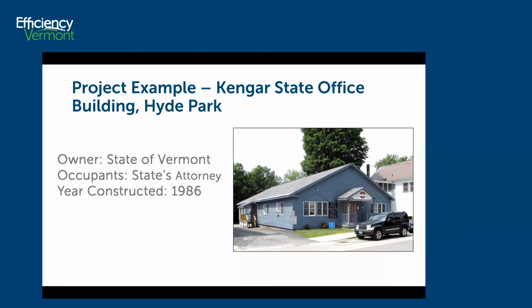Okay. So my project example, I work a lot with the state of Vermont on existing state buildings, and we look at buildings. We primarily have been looking at buildings that have high energy use index, so your kBTU per square foot. But every once in a while, we get a building audit request that comes through for us to go take a look at it. And this state office building in Hyde Park was an example where it wasn't an issue of the energy use index. There was another reason why they wanted us to look at going with heat pumps. So the reason why I decided to use this project as an example is that there is nothing special about this building. It is your typical office building, built in '86, wood studs.